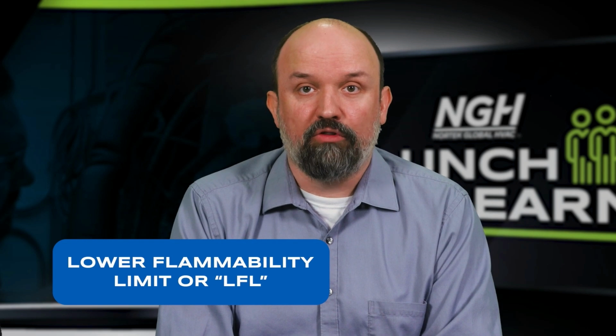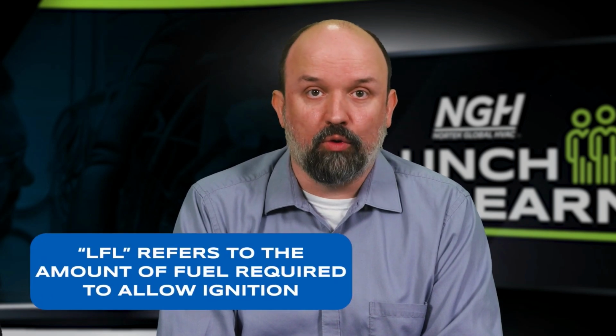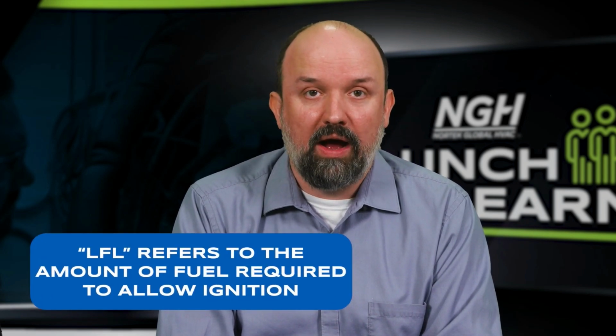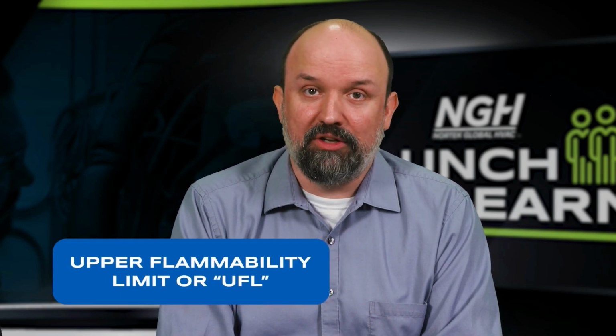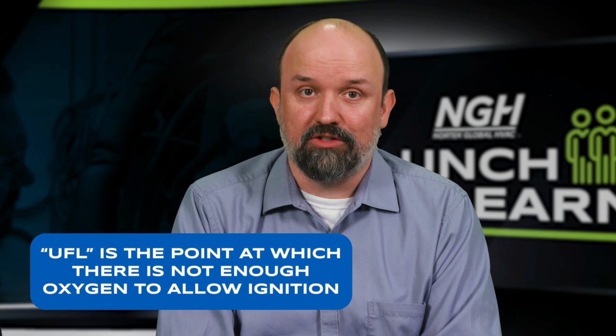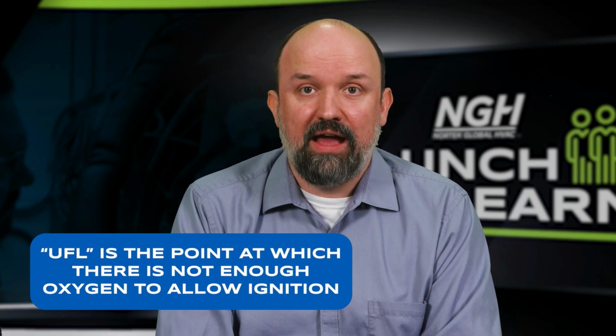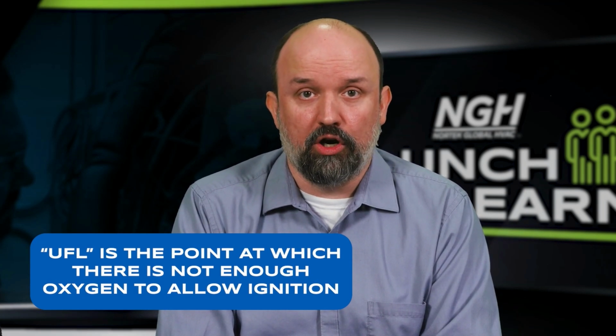The LFL refers to the amount of fuel, R454B in this case, required to allow ignition. There is also an upper flammability limit, or UFL, where there's plenty of fuel, but not enough oxygen. Outside of that range, no ignition will occur. Think of it like this.